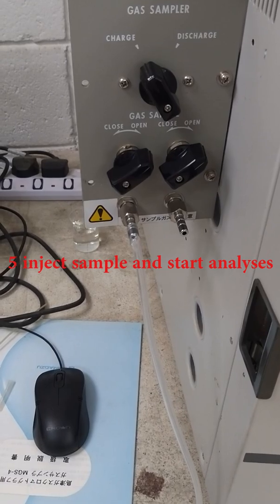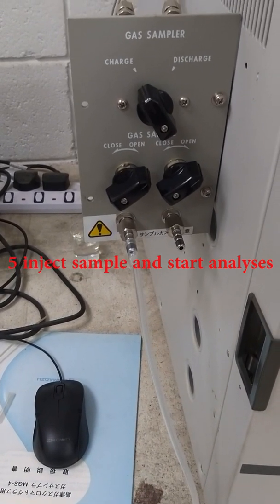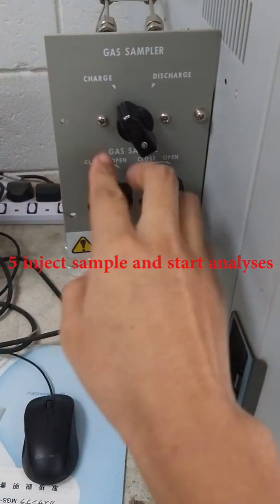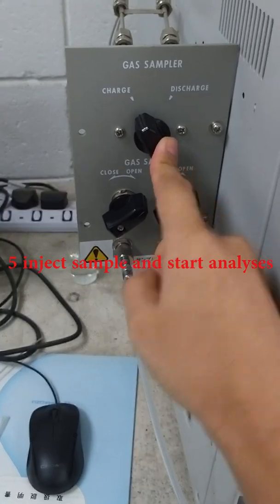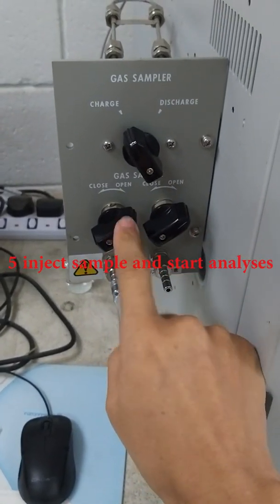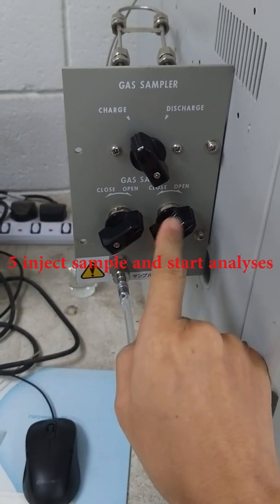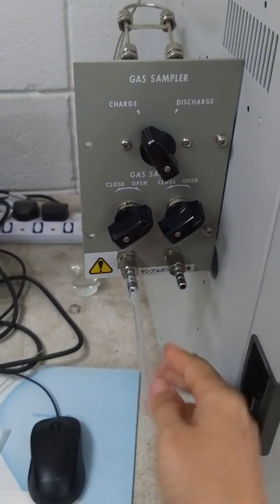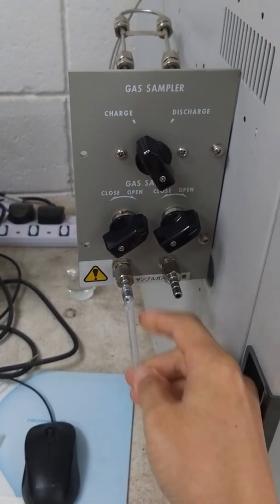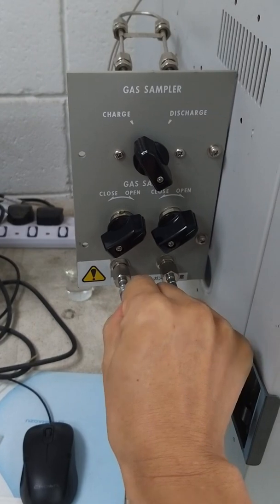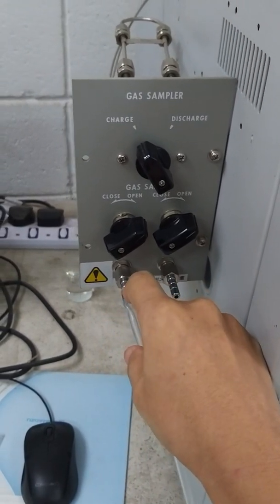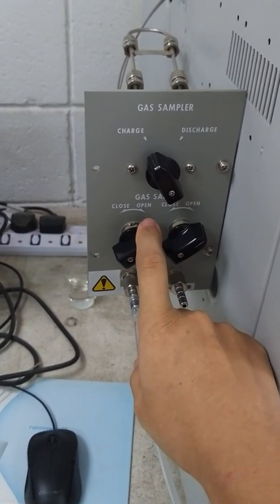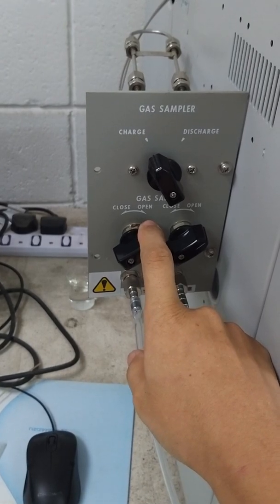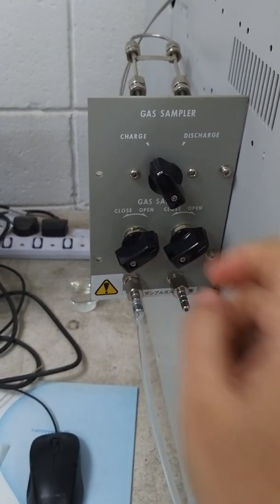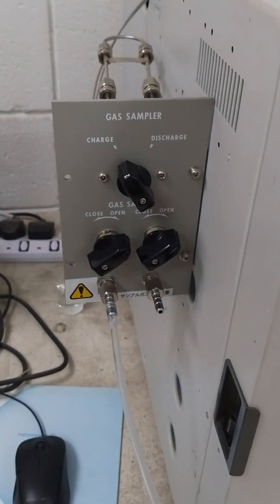The gas sampler is used to charge the sample into the sampler. Adjust this valve to charge. Open the gas in, open the gas out, and charge the gas. After a few seconds, after the gas sample is fully charged, you can click close the gas in. After a second, close the gas out to finish the sampling.